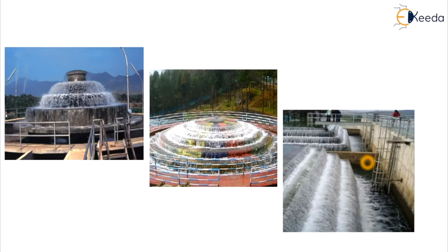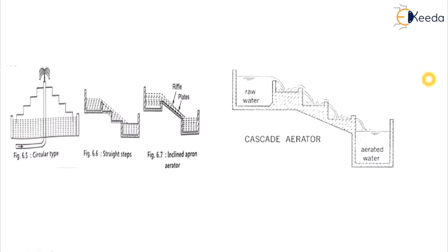The cascade aerator increases dissolved oxygen in water and strips dissolved gases from it. It is a natural flow aeration system that consumes less energy than forced aeration systems, making it economical. The first two images show the circular type cascade aerator and the third shows the rectangular type. Water is pumped through a central pipe and flows as a thin sheet through a number of steps, coming into contact with air for gas transfer. These are the types of cascade aerator.